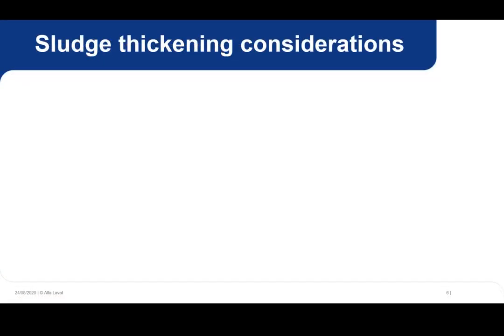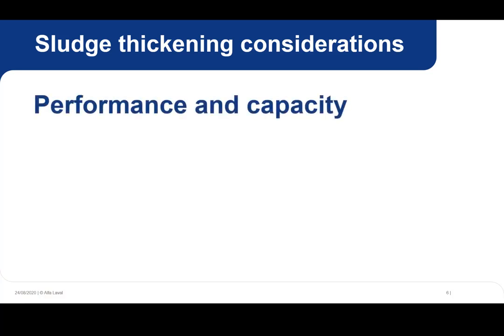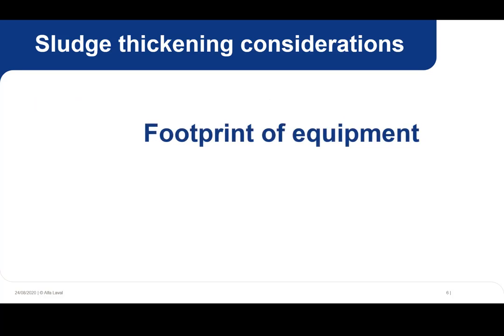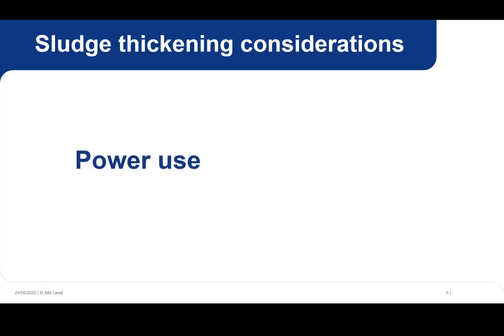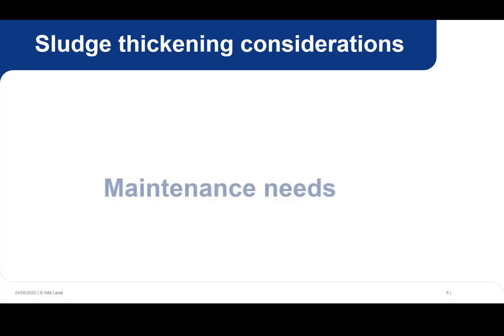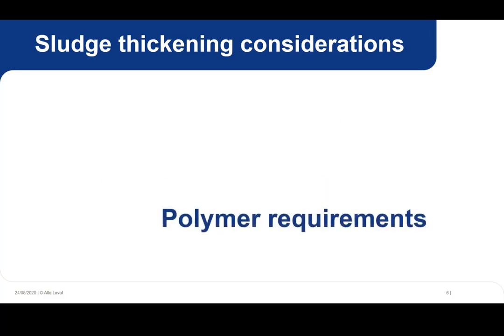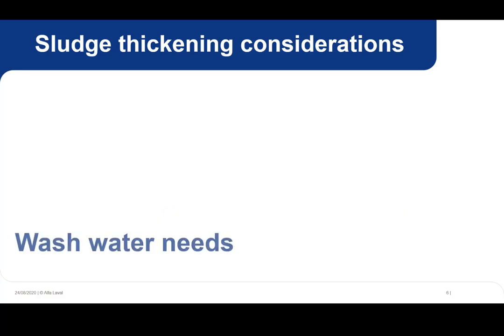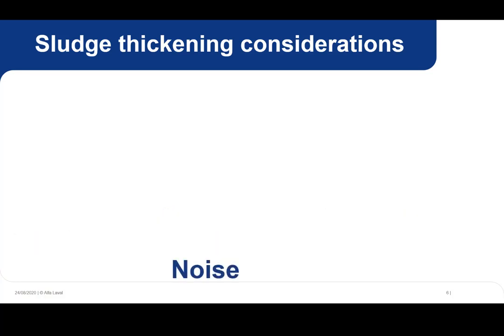Let's start by looking at some sludge thickening considerations. Of course, performance and capacity are table stakes metrics. The equipment has to be able to do what you need it to do both now and in the foreseeable future. Footprint can also be really important, as space and real estate are often in short demand. Keeping power use down can help with the long-term costs, and of course the ongoing maintenance needs of the machine can have big implications to a budget, as well as the amount of polymer used, as this is a significant expense in many operations. Finally, you have things like wash water and noise requirements, which can sometimes go unnoticed but can add up. And of course, operator safety and health are always a concern.